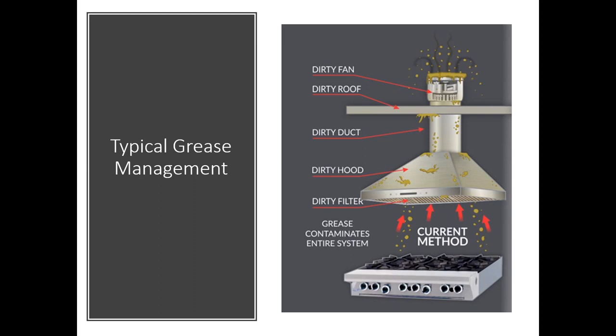Many methods of cooking produce some amount of airborne grease particles that are pulled into the kitchen exhaust system. The initial line of protection is your standard baffle filter that captures 25 to 30% of these particles before they enter the hood and duct areas.